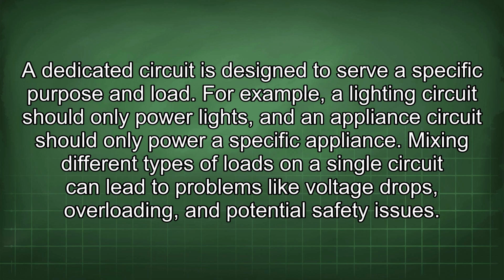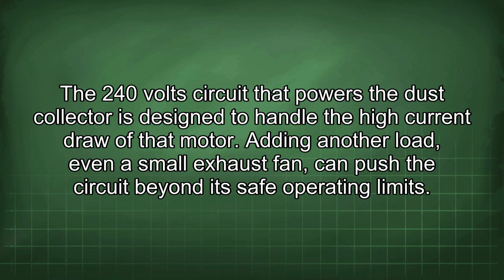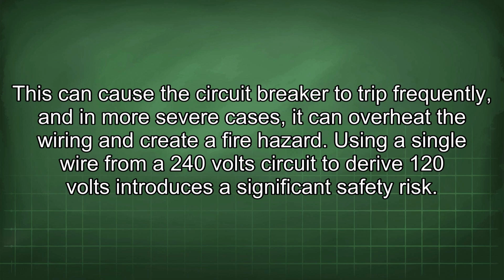Mixing different types of loads on a single circuit can lead to problems like voltage drops, overloading, and potential safety issues. The 240-volt circuit that powers the dust collector is designed to handle the high current draw of that motor. Adding another load, even a small exhaust fan, can push the circuit beyond its safe operating limits. This can cause the circuit breaker to trip frequently, and in more severe cases, it can overheat the wiring and create a fire hazard.